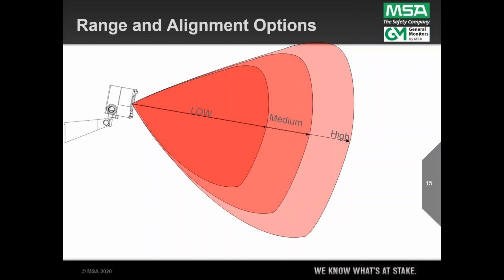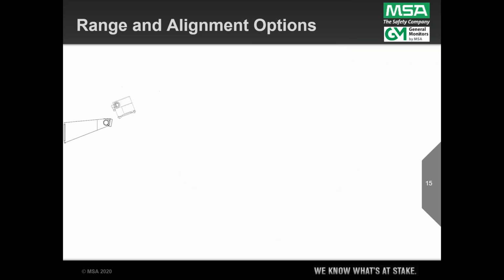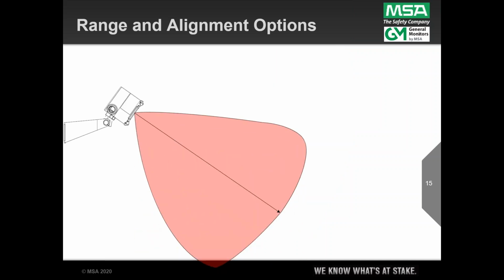But what I've seen as a field service tech is that so often the flame detectors are not aligned, and the field of view is not controlled like it should be. So a lot of times, when I was actively doing this, I would end up at a site changing the field of view, and I would use a laser aiming device to identify the 12 o'clock, top dead center, vector of sensitivity. So I'm controlling that and not allowing it to get out into the horizon and outside of the facility.